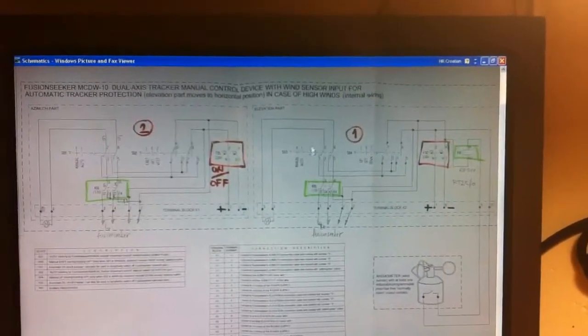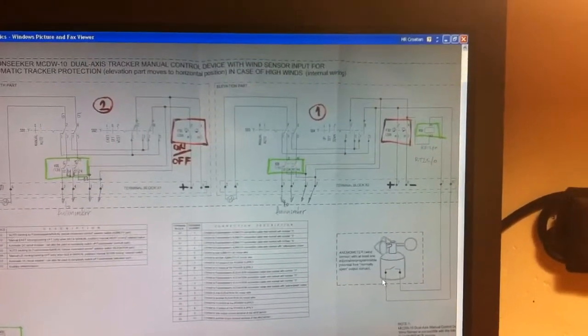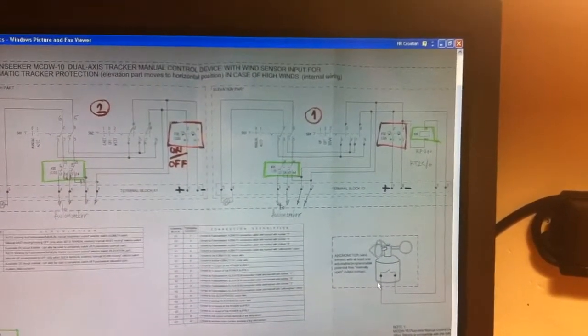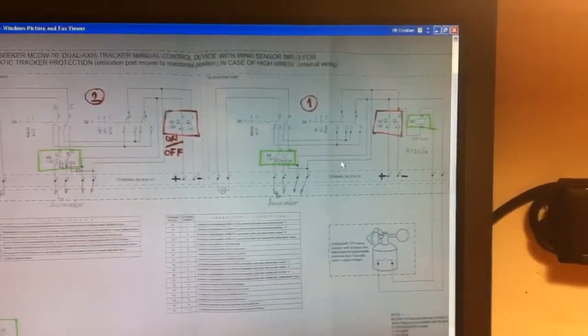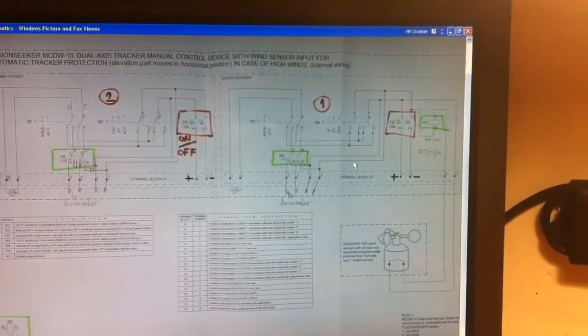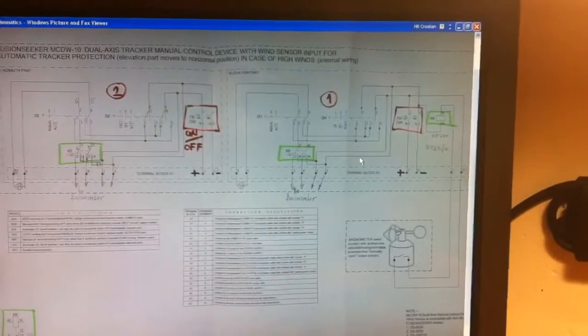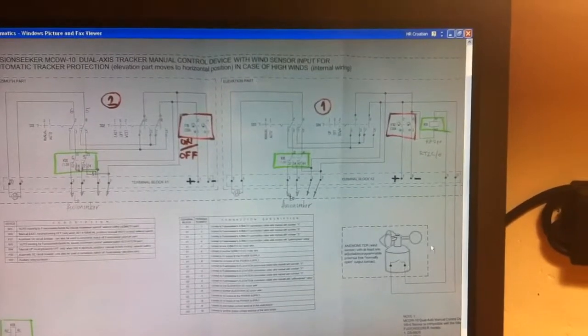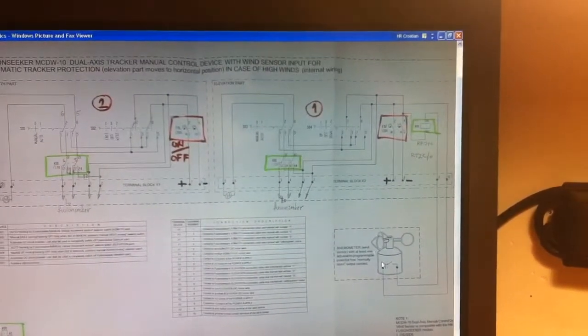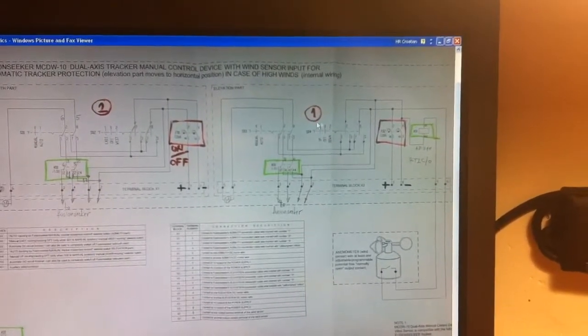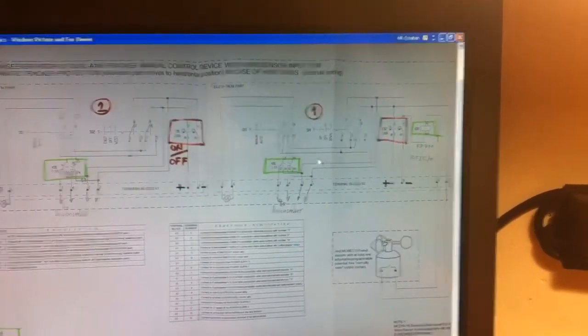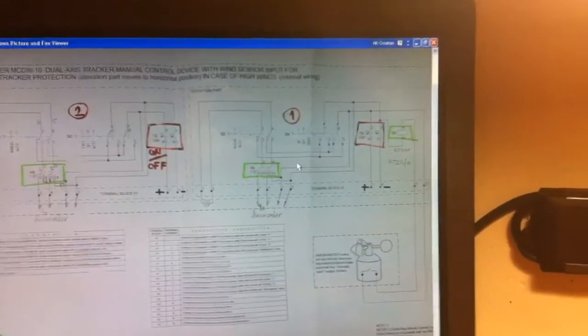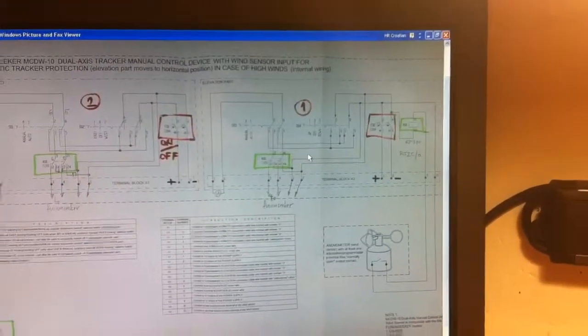And on the elevation part, there is an option for anemometer, which gives the signal to the control board that the photovoltaic modules must be positioned horizontally in order to prevent damage from the wind. So when the anemometer senses high wind speed, it shuts this contact and gives information through the control board that the motor should rotate the photovoltaic panel horizontally so that wind blows have no influence.